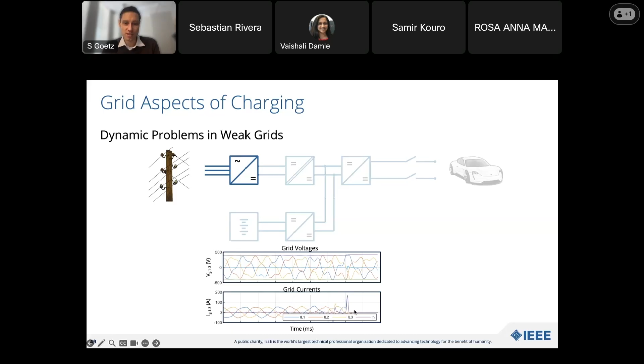Why is that the case? Well, your chargers, power supplies, and solar systems all use switch mode electronics, and they're usually constant power. If the voltage decreases, they don't necessarily adjust like a conventional load, but instead control to constant power and adjust the current to keep the power constant.